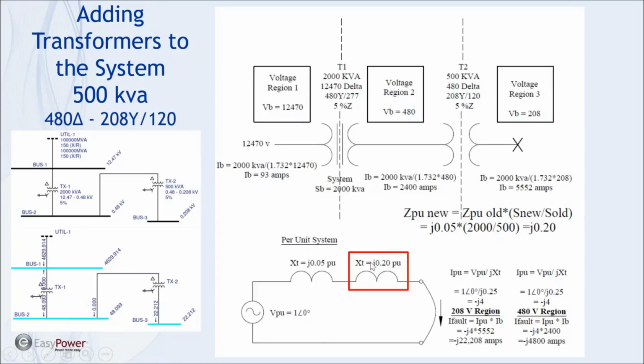My 2 impedances add together. So in my 208 volt region here, my fault current is 1 over J.25. That's the sum of these two, which gives me, multiply that out, we get minus J4. Multiply that by the base current in the 208 volt system, and my available fault current now is 22,208 amps. Okay. The same fault in the 480 volt region now amounts to 4,800 amps. That would be in the 480 volt system. And I'm really only looking at the low voltage systems.